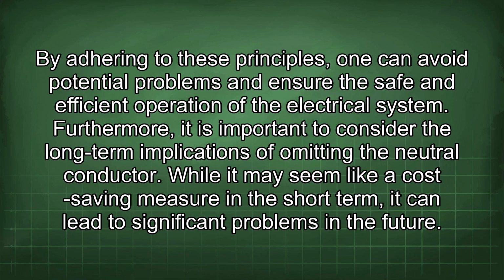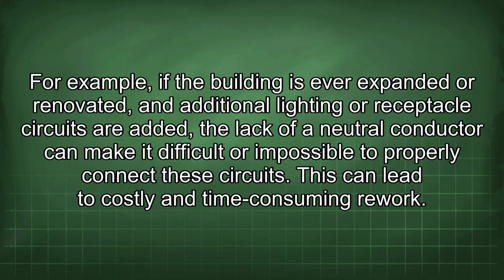While it may seem like a cost-saving measure in the short term, it can lead to significant problems in the future. For example, if the building is ever expanded or renovated and additional lighting or receptacle circuits are added, the lack of a neutral conductor can make it difficult or impossible to properly connect these circuits. This can lead to costly and time-consuming rework.